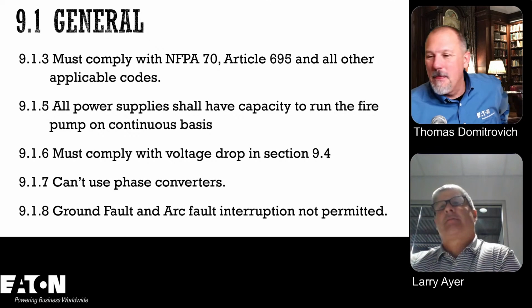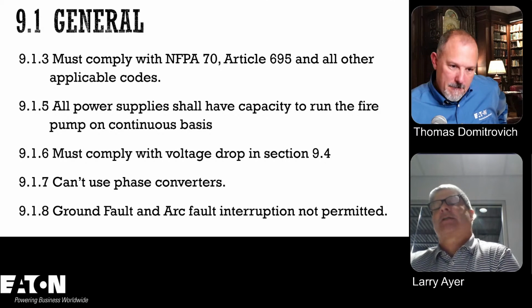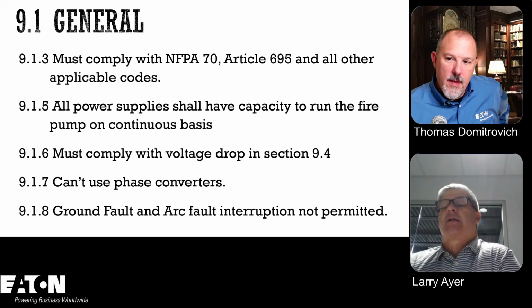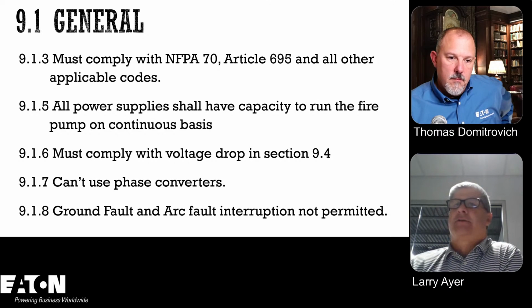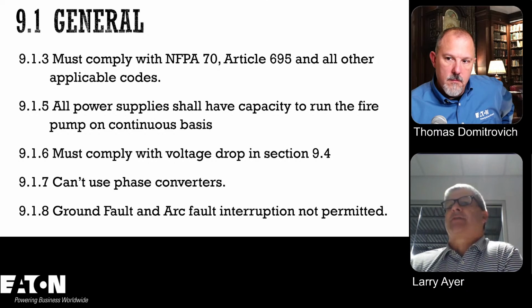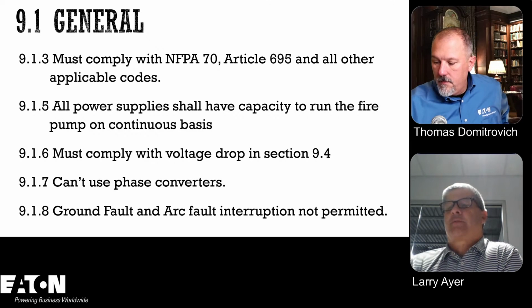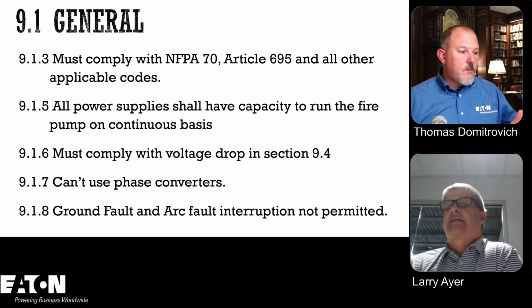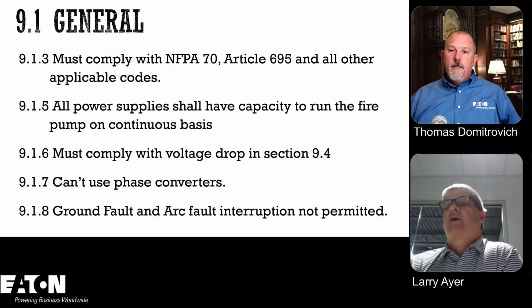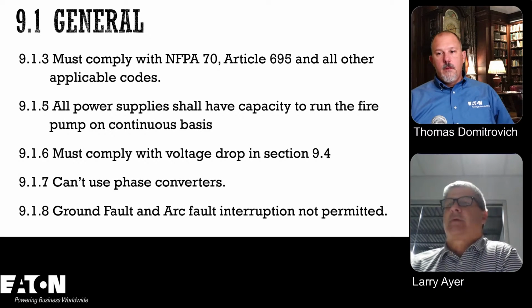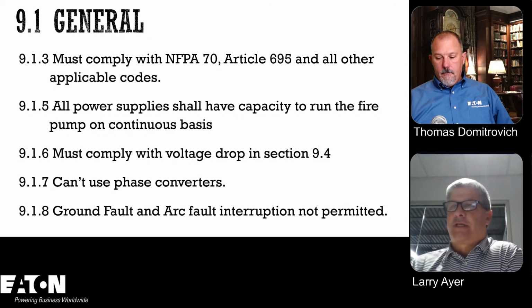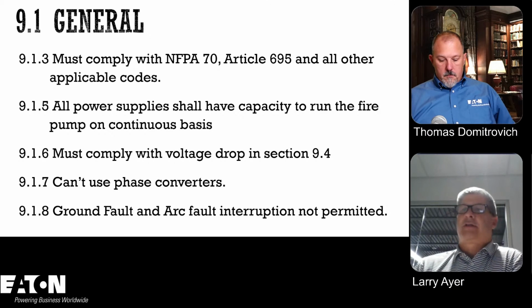But you look at the same thing with fire alarm systems, right? And if you look at 760, I think the general concept is the same language. You don't want to have arc fault or ground fault protection on circuits that are feeding things that have to do with fire alarm. I think they don't want any possibility of nuisance trip, and I think that's why they're trying to avoid these technologies on these feeders and this protection.